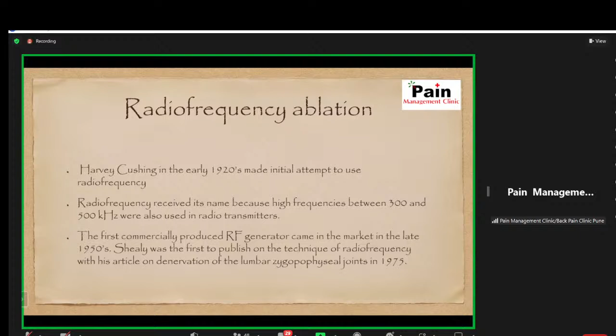When we talk about radiofrequency ablation, this is an old technique. Shealy used it in the facet joint in 1975. Commercially, it has been available from 1950. So what is the mechanism? As Dr. Dhruva was telling, the radiofrequency technique consists of an electrically generated source applied to an insulated electrode. The electrode is insulated and the tip is active. This high frequency causes friction of the ions inside the tissue, and that generates the heat.